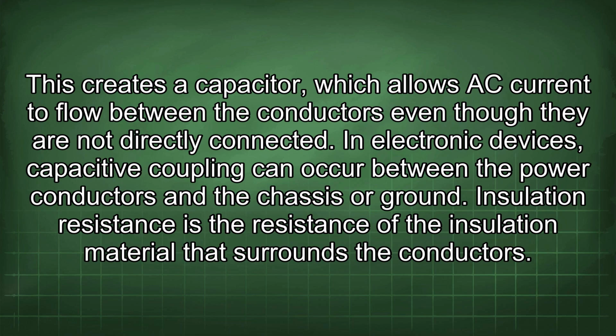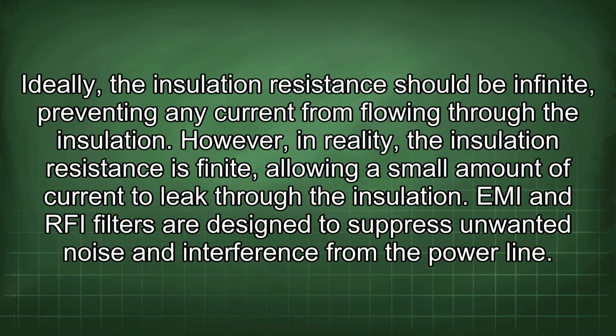Insulation resistance is the resistance of the insulation material that surrounds the conductors. Ideally, the insulation resistance should be infinite, preventing any current from flowing through the insulation. However, in reality, the insulation resistance is finite, allowing a small amount of current to leak through the insulation.